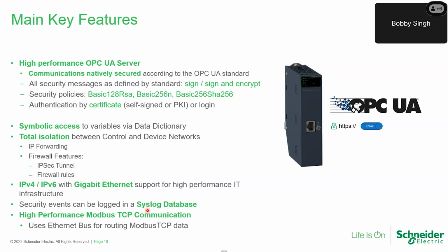Lastly, the NUA module handles Modbus data over the Ethernet bus instead of the X bus, providing you high performance. It's transferring all the Modbus data at the speed of 100 megabits per second over the Ethernet bus, versus, remember, on the NOC modules, they're using X bus.